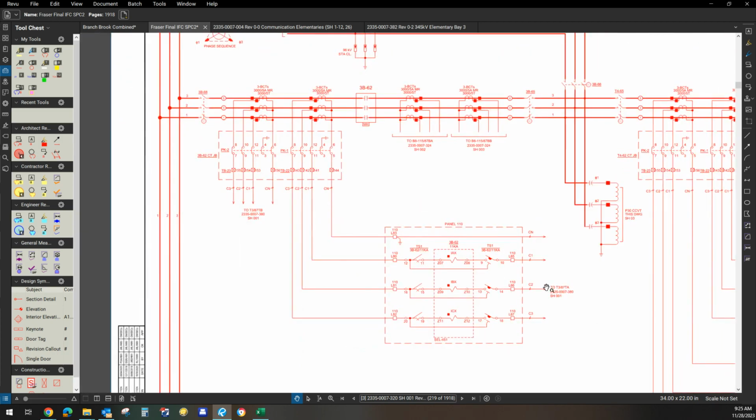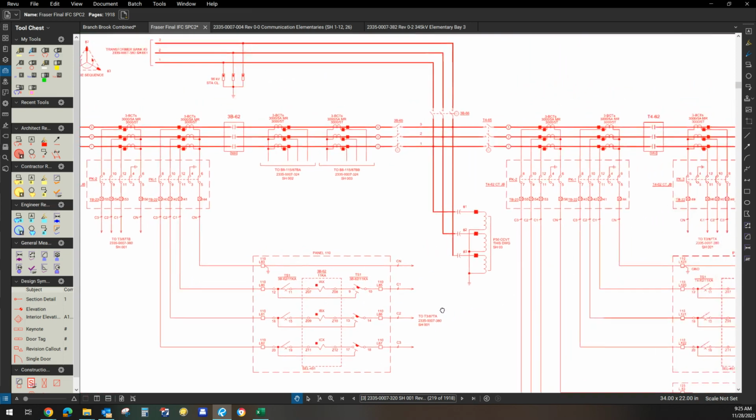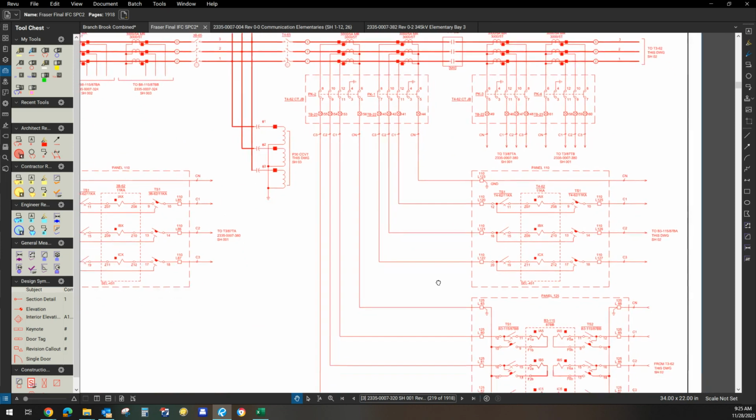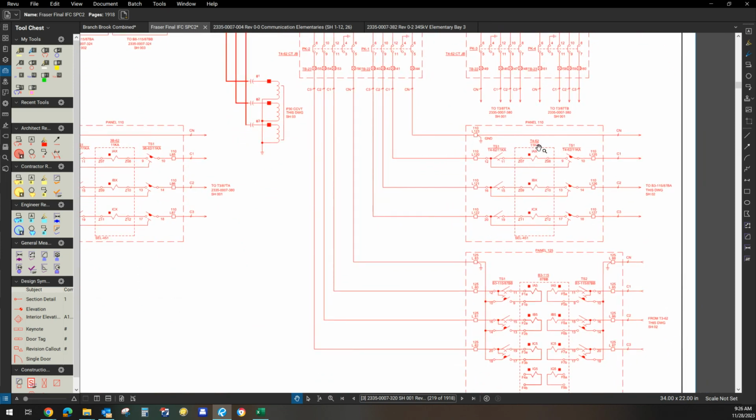And I would just look at each one of these, just so in my mind it makes sense. I have to first go through a test finger, then into a relay, out of the relay, into a test finger, and back to the terminal block. Okay, I'm going to look over here and make sure all this makes sense. Okay, everything looks good.